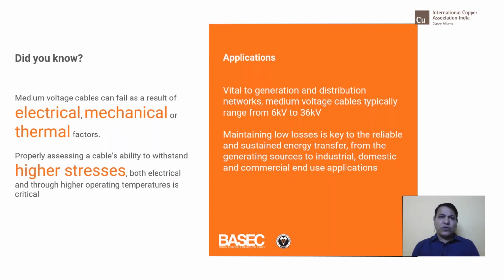The cable sector is the core of the power industry, and if something were to go wrong, it can have a huge impact on business and, more importantly, safety risk. Electrical, mechanical or thermal factors can contribute to a big failure of a cable. Problems in these areas can be increased to an extraordinary level if the cable has not been manufactured to the right national or international standards to perform continuously to its technical merits of the application.